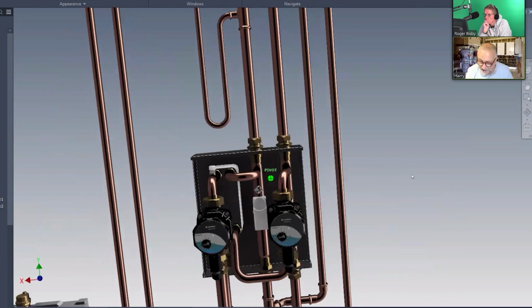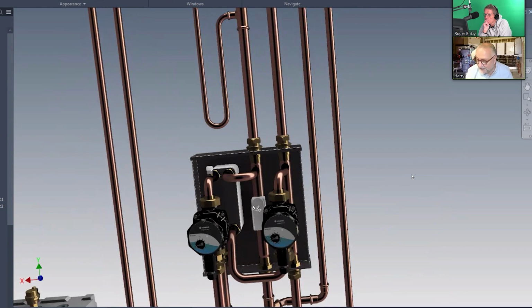But now there's a T taking this pump away, and we have a stat, and a stat should never, ever be on the flow. A stat should always be on the return, and 55 degrees is when it condenses. So if you put a stat on the flow, and if you start the pump at 55 degrees, you're causing condensation in the boiler, which is rusting the heat exchanger. Yeah. So this stat reaches 55 degrees. It turns on both pumps.